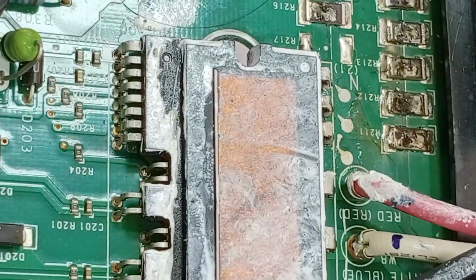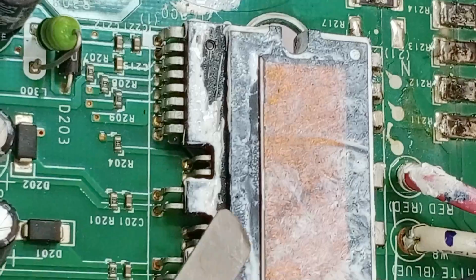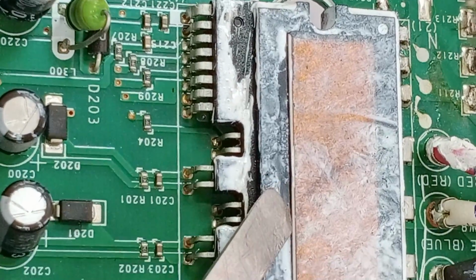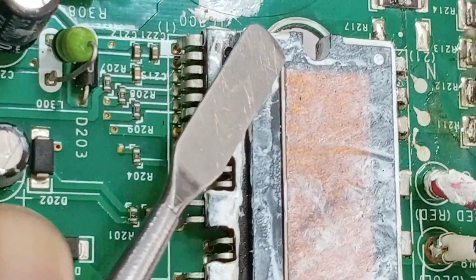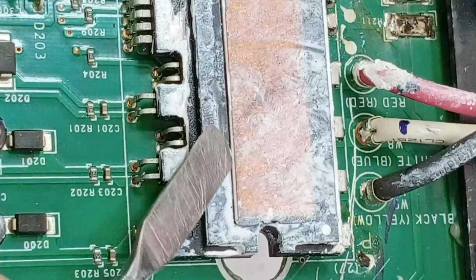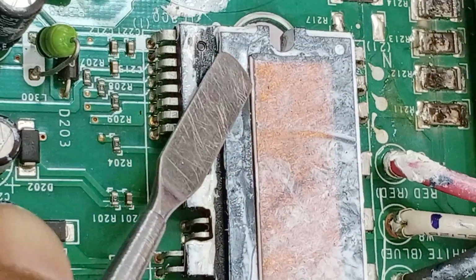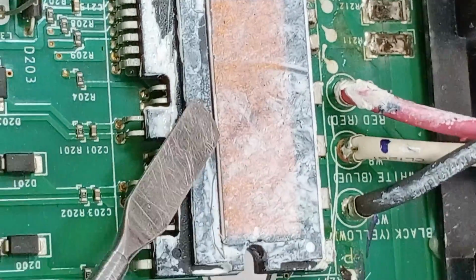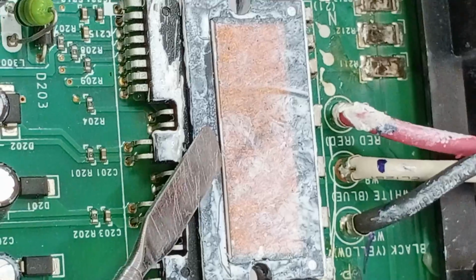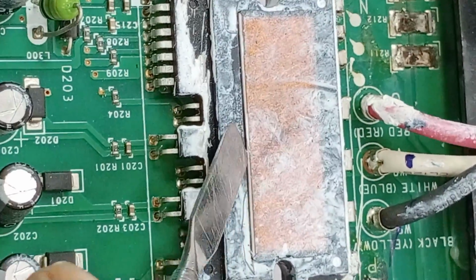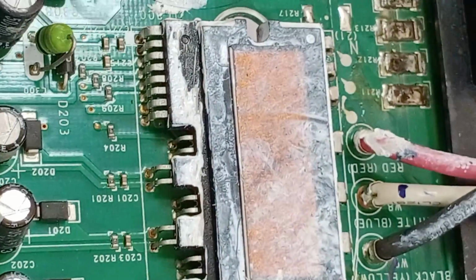If I look at the IPM physically before testing it with the multimeter, it fails the physical test. The IPM module has bloated up from here. A clear gap can be seen here, which is not a good sign. Normally, the IPM has no gap between them. The scraper is going inside it. This is clear that the IPM module is not fine and has failed.